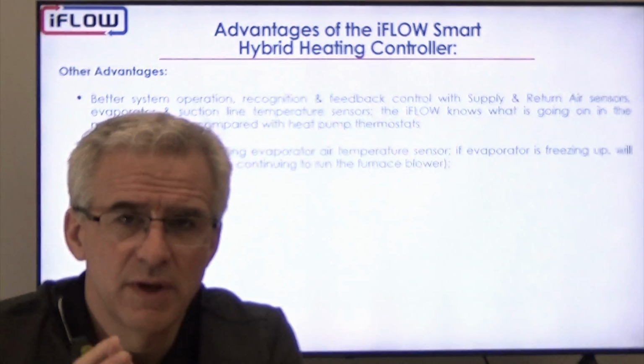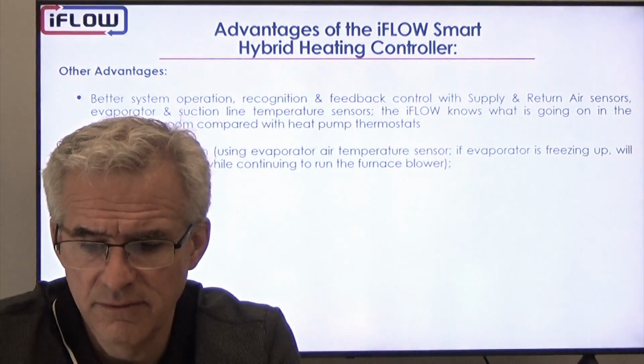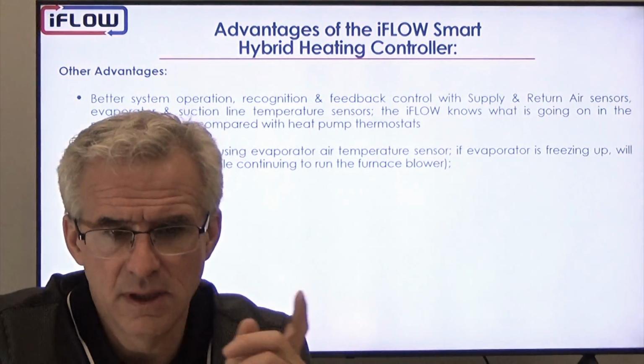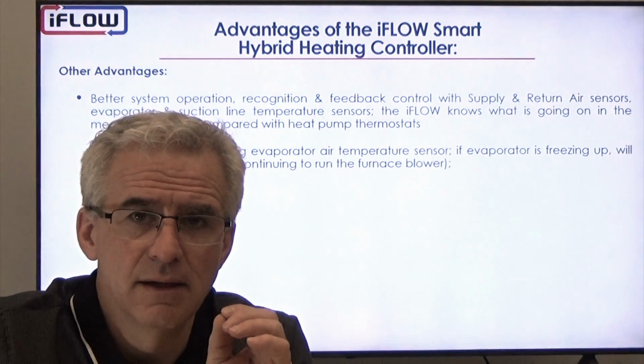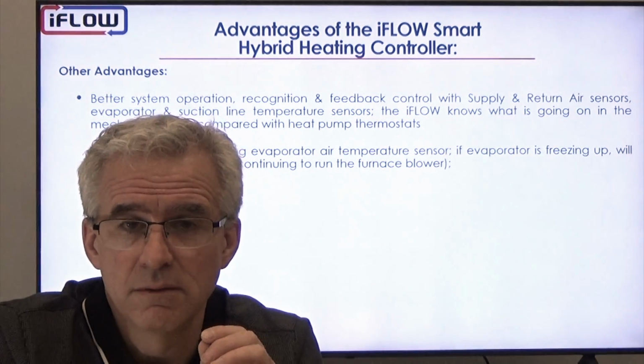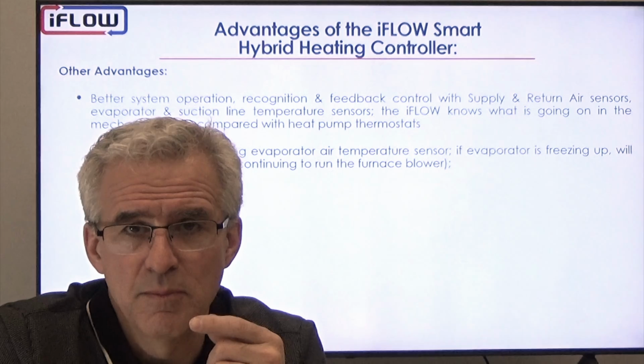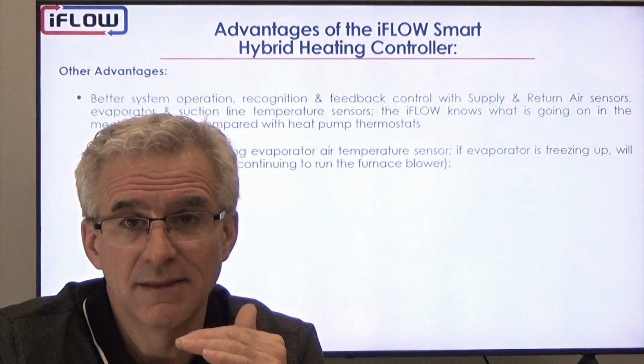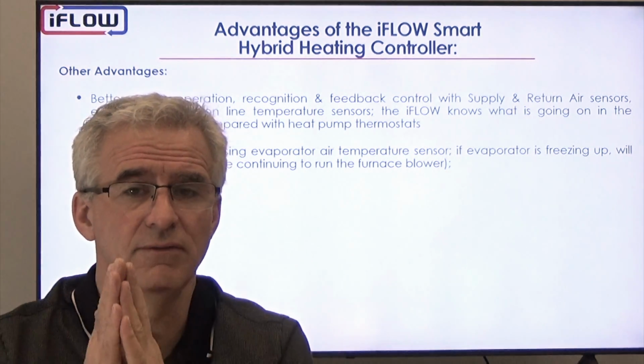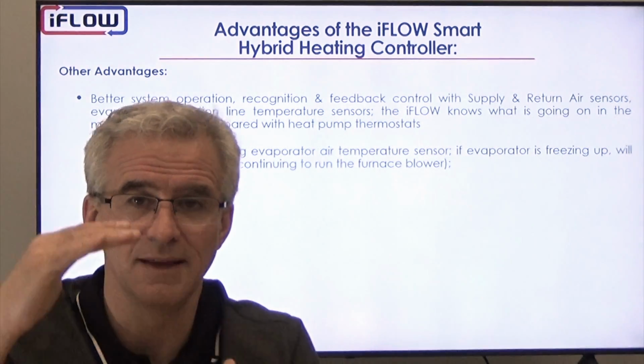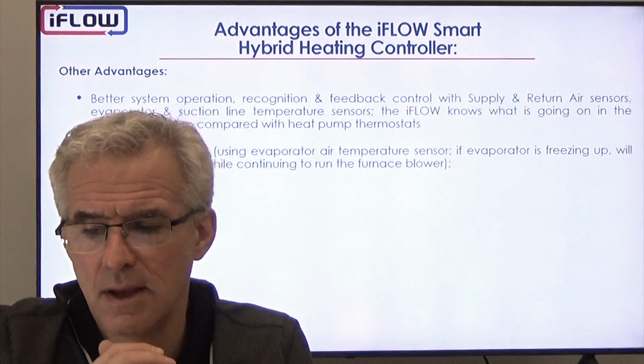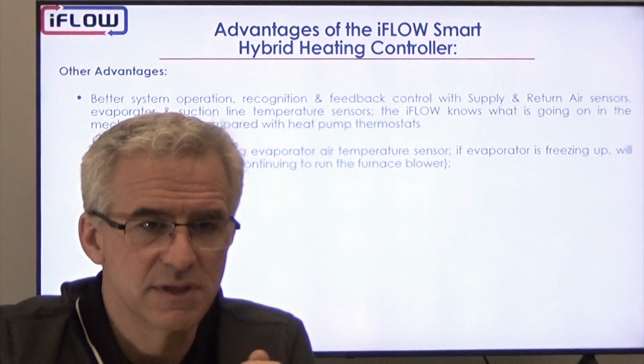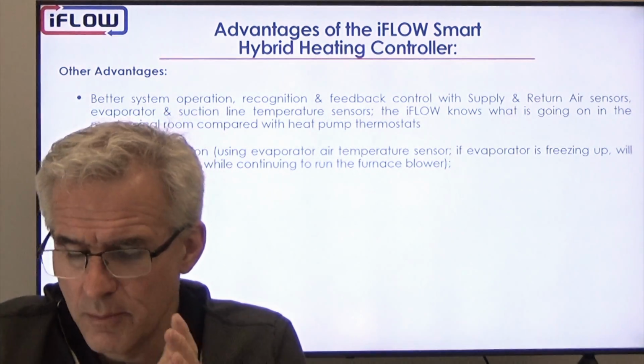With those sensors, we have freeze protection built into the iFLOW. So we use the evaporator air temperature sensor that will connect to the top of the evaporator coil, and it's looking at the temperature coming off the top of the coil so that we can look at the delta T across the coil to assess whether the system is operating properly.